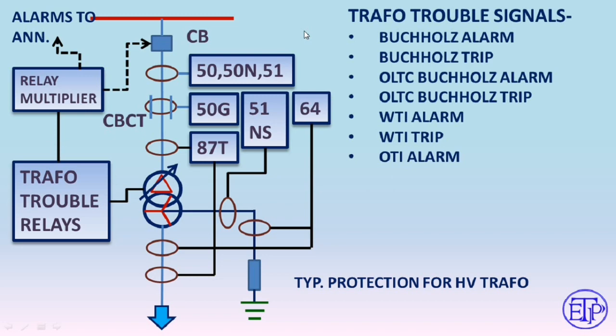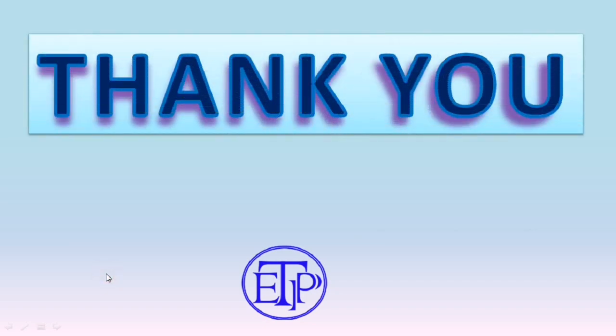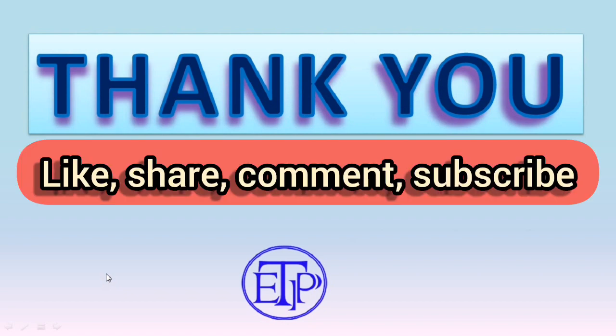All transformer trouble signals generate normally-open (NO) type contacts. When the relay operates, the NO contact converts to NC. Inside the switchgear, contact multipliers using electromagnetic relays expand these contacts. Trip signals are then sent to the circuit breaker, and alarm signals are sent to the annunciator switchboard. This is how transformer protections are taken care of. I hope you have enjoyed this video and learned about transformer protection and how the single-line diagram is made.